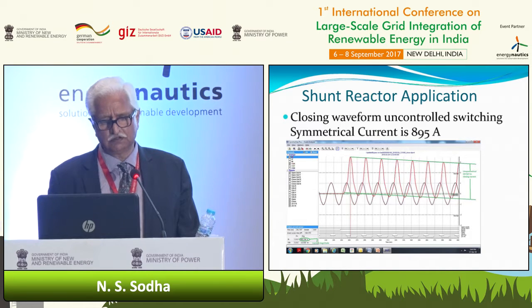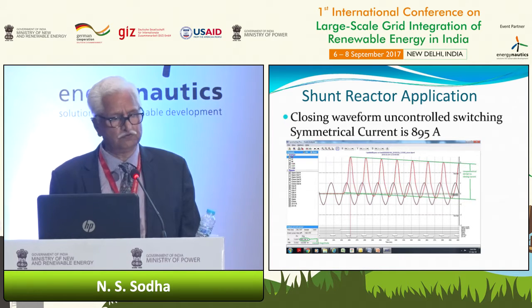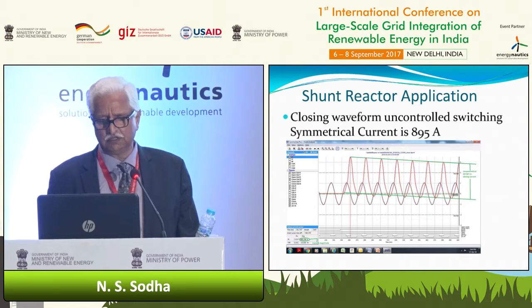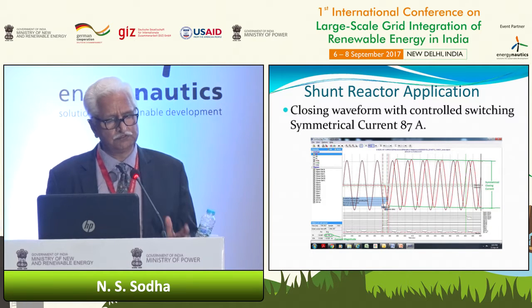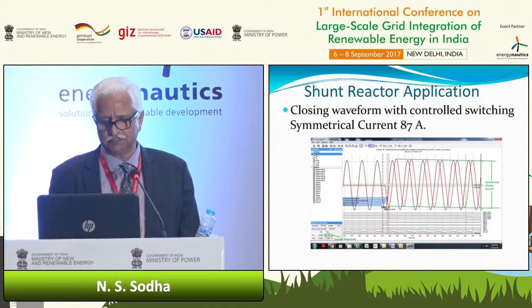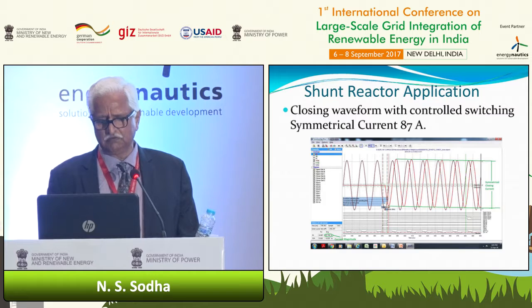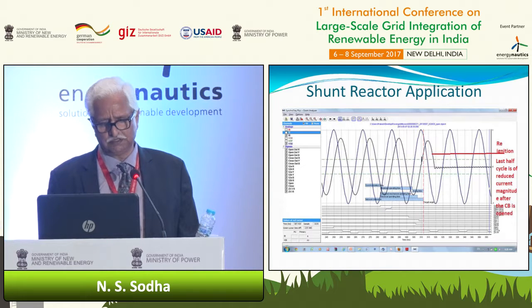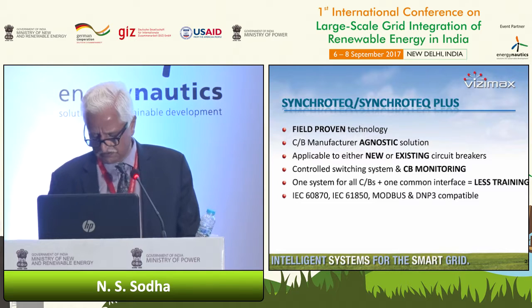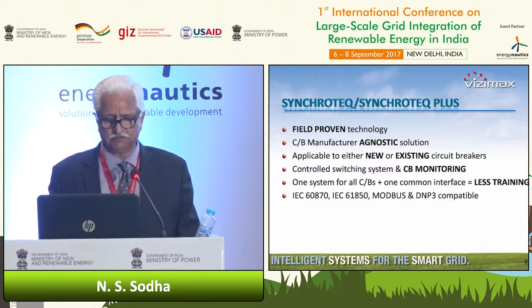And you can see here the closing waveform was uncontrolled switching. Symmetrical current is 895 ampere before the application of the CSD, and then it came down to 87 ampere. So definitely the primary equipment is becoming safer by adopting the control switching devices application. Now, as a waveform, we have open waveform with the reignition by the control switching, and so in most of the control switching activities, we are installing these CSD devices or the control switching devices.